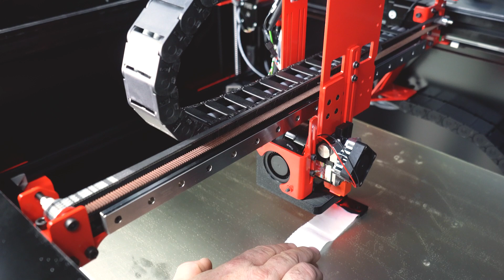Now, be very careful with these screens. If you're doing this from the web interface, you can do this from either the screen or you can do it from the web interface. The farmost button on the left interface is 20 millimeters. I recommend doing this from the console on the screen in front of the machine because the first button is 2 millimeters. Be very careful at this point which button you're pushing because the safety mechanisms for this machine that will not allow it to move so far are turned off during this macro. So if you tell this to move 100 millimeters in the negative direction, that is what it will do.